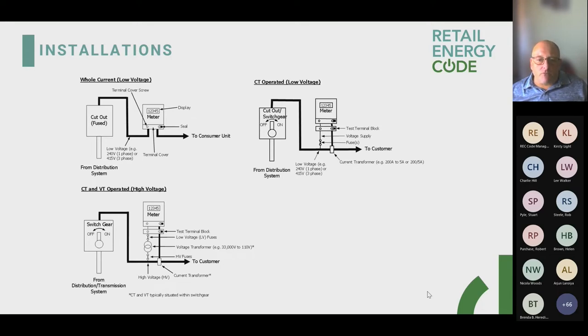So we cheat. The main cables go straight to the customer, so the customer is permanently on supply. What we do is wrap what we call a current transformer around the cable, and we only monitor 5 amps worth of the current. The reason we do that is so the metering can remain small, the equipment can remain small, and it doesn't take up as much space, but also it allows for the customer's equipment to be permanently connected. For some of these organisations, that's essential - if you imagine that metering system was in a hospital or somewhere like that, I can actually isolate that current transformer, change the meter, and the customer doesn't lose any power. It means they can remain on all the time.